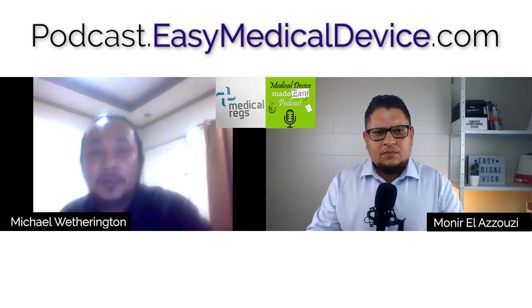You should know more about your risk, to identify your risk and be able to show mitigation for those risks, right? So that's why the standards should be used as a risk mitigation. For example, if electric shock is a hazard, then you mitigate that through the leakage current requirements per IEC or EN 60601. So it may not be that you would have to apply the entire 60601 standard, because a certain risk may not be present based on your design of the device. So there may be areas there that may not be applicable.